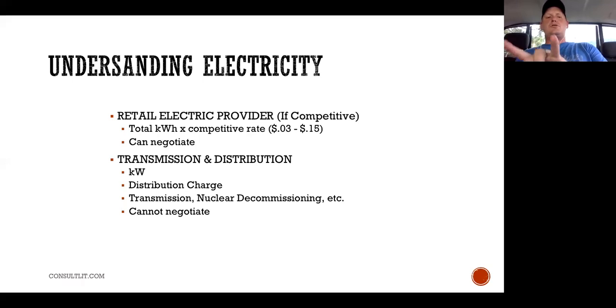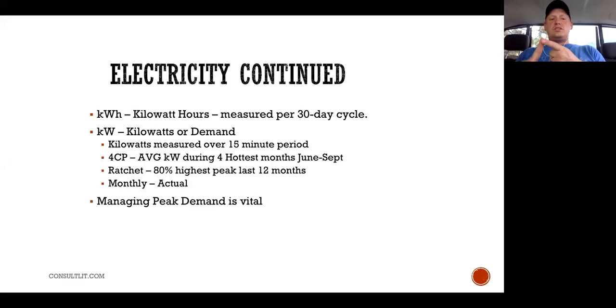I won't get into this too much, but two things I want you to know: kilowatt hours is the consumption, the amount of energy you use during a 30-day cycle. Kilowatts is the rate at which you use electricity. If you look at your bills, you all have a kilowatt demand charge. If I break up my month into 15-minute sections, your utility bill will find the highest 15-minute section, and that's what you're charged for the month. So even if you average 200, and all of a sudden you turn everything on and that 200 moves to 350 just for 15 minutes, you're not charged the 200 average, you're charged the 350.